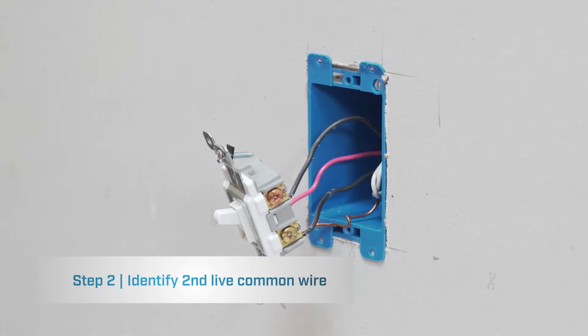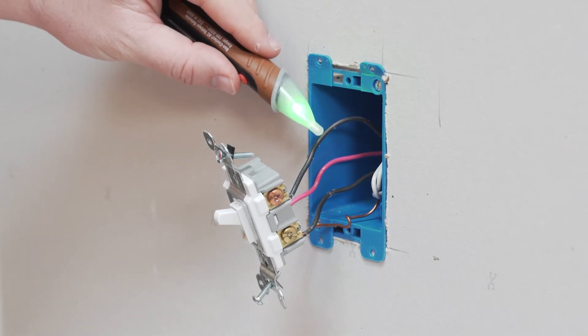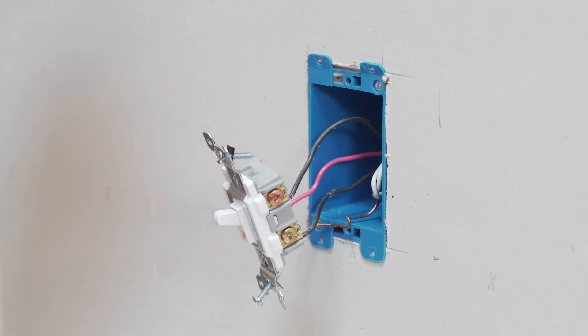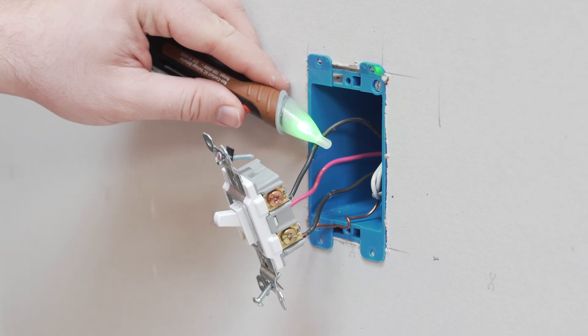Next we'll test the second location. We only need to test the common wire to determine whether or not this is going to the fixture or coming from the circuit breaker. We already know from the previous box that it has the circuit breaker, so this is going to the fixture, and you can confirm this by testing it.